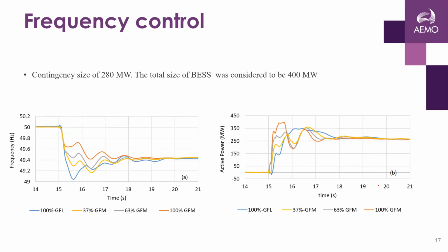This is the test system where there is a loss of generation. If you have all the battery in grid following mode with FFR enabled, you can see the frequency goes all the way to 49 for this specific size of system and this specific generation contingency. If you have all of them in grid forming mode, it stabilizes a little bit quicker, at least it's not reaching 49 hertz. On the other side, this is the response from the battery itself.